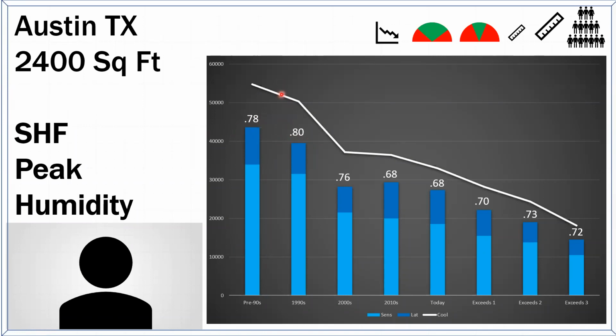Call that 0.79 - 79% of the load on a peak day. So you design on your hot day. What happens when the very humid day comes around? It's a little cooler. How much cooler? Well, cool enough that it's about 80% of what your peak load was, which means your system is going to run 20% less on a day that you need it to run a lot. This is what it used to be.